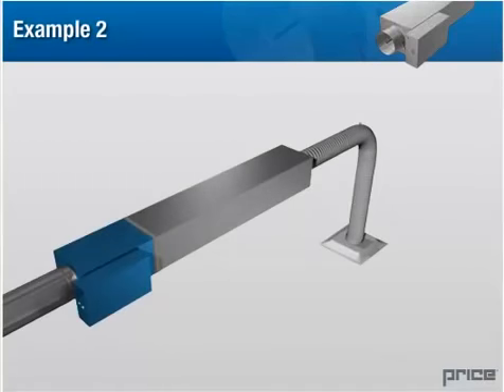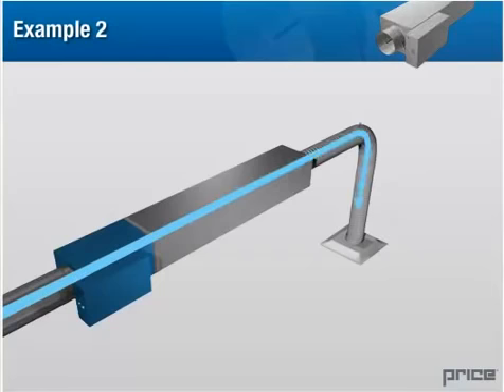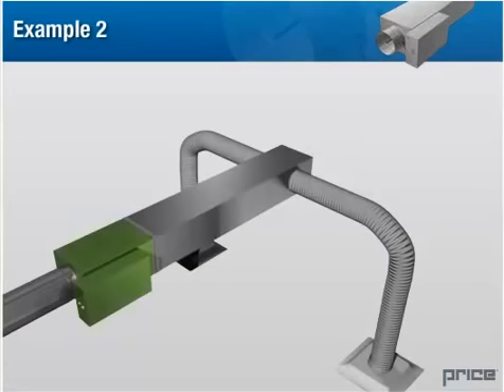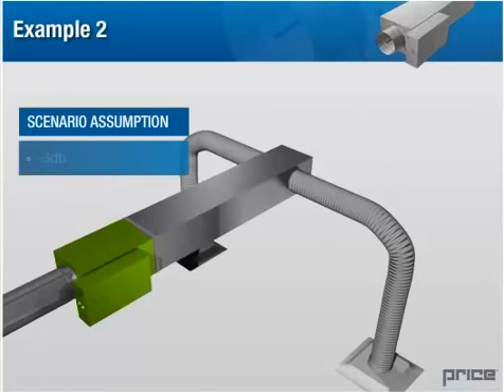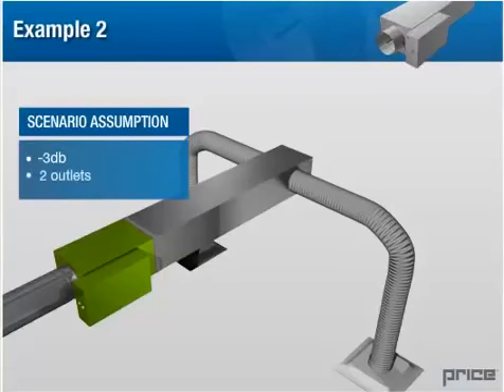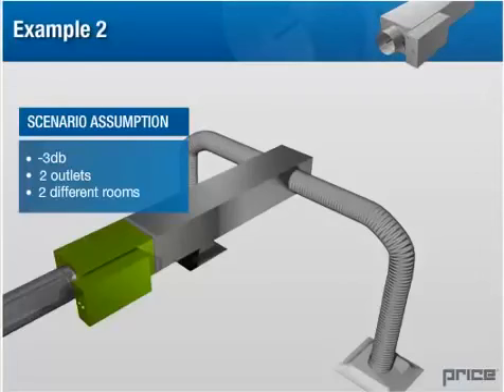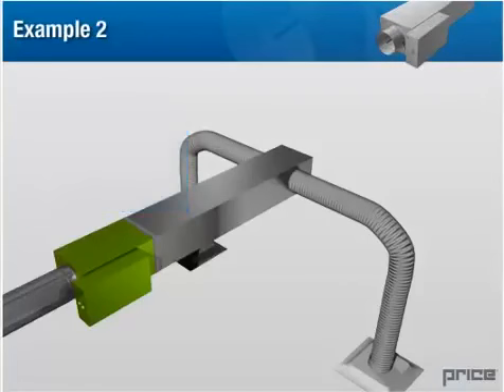Here's why. The small terminal unit is assumed to have just enough airflow to be supplying only one outlet. This means that all of the sound power being discharged by the terminal unit is traveling down this one duct and into the room. When we look at the medium box, we can see that an attenuation value of 3 is allowed. This is based on the assumption that we are providing enough air through this terminal that there would likely be 2 outlets in the system, and they are probably providing air to different rooms via 2 equally sized ducts. Therefore, ARI 885 allows for a 3 decibel sound power split.